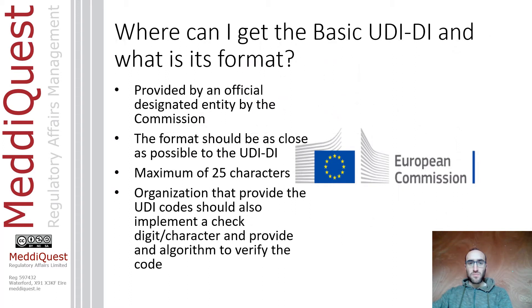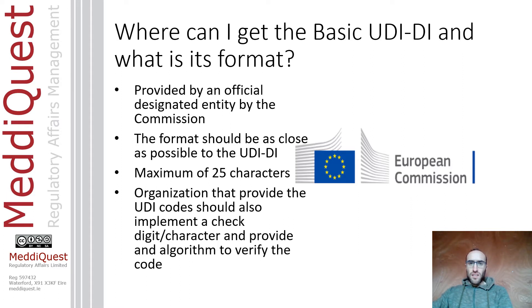The UDI is provided by an official designated entity appointed by the Commission. The Basic UDI-DI format should be as close as possible to the UDI-DI, with a maximum of 25 characters. The organization providing the UDI code should also implement a check digit character and provide an algorithm to the Commission and the manufacturer to verify the code.